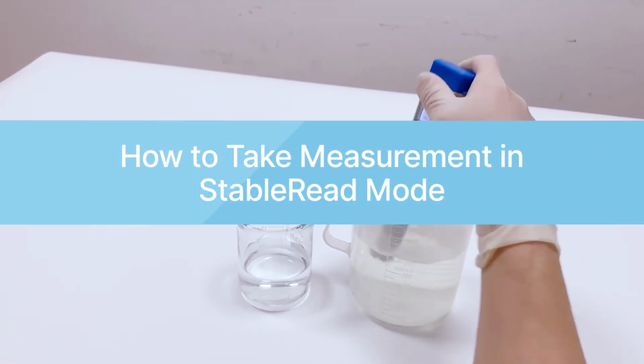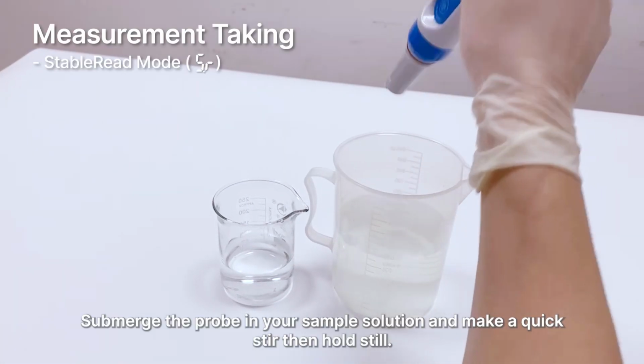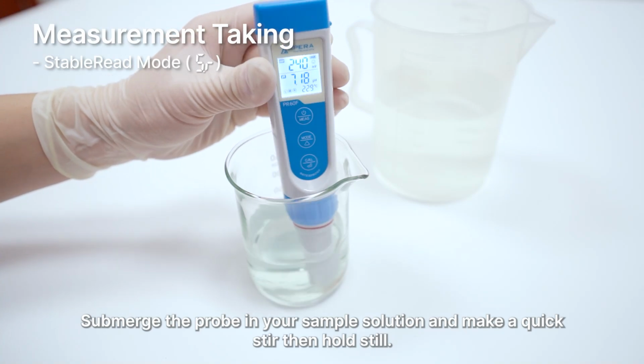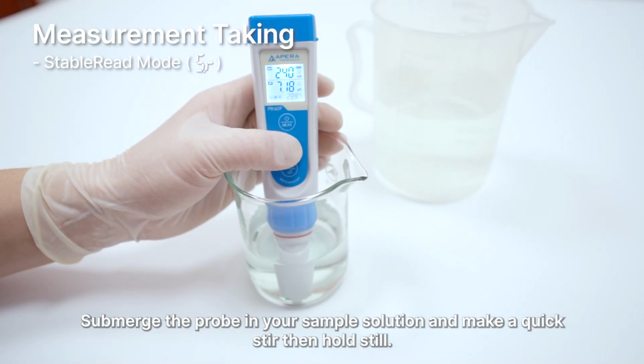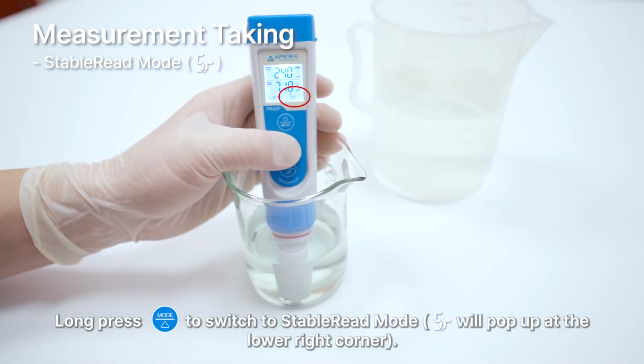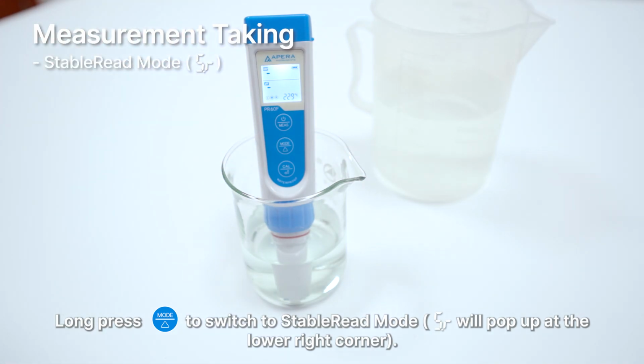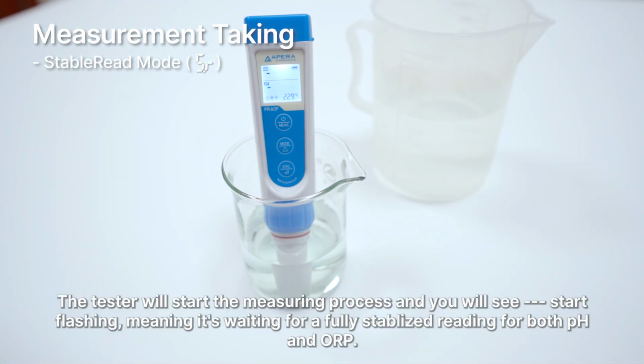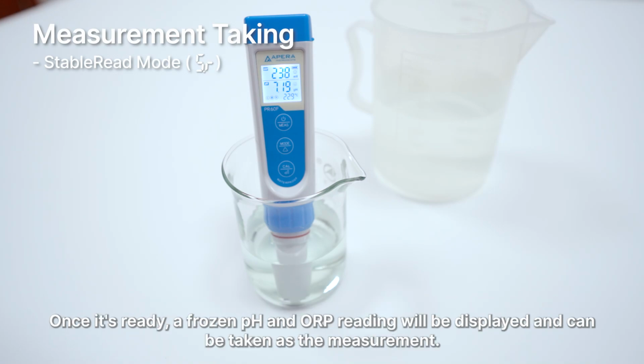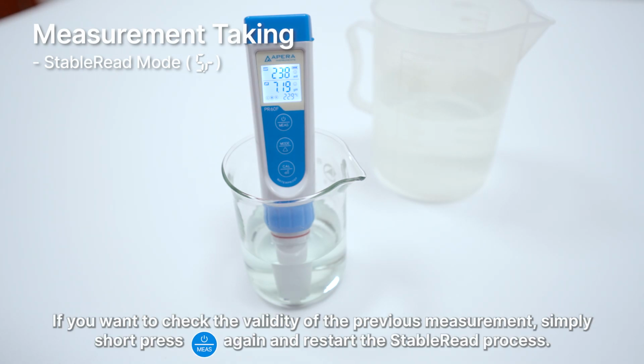How to take measurement in stable read mode. Submerge the probe in your sample solution and make a quick stir, then hold still. Long press mode button to switch to stable read mode. SR will pop up at the lower right corner. The tester will start the measuring process and you will see the dots start flashing, meaning it's waiting for a fully stabilized reading for both pH and ORP. Once it's ready, a frozen pH and ORP reading will be displayed and can be taken as the measurement.